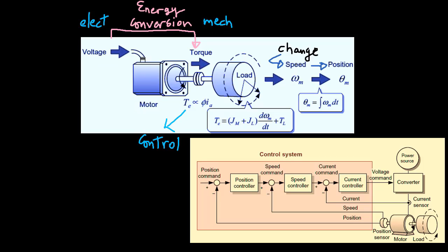Therefore, in motor drives, the most effective way for controlling the position or speed of the load connected to the motor is to control the torque of the motor directly. However, the torque control is expensive, due to the high cost of the torque sensor for motor torque feedback.